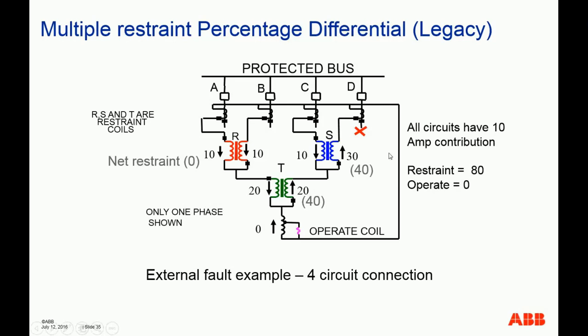I can't discuss too much, but the idea is, when the current passes through the restraint winding in the same direction, the net restraint is 0. So basically they are subtractive. If the currents pass through the windings in different directions, as in this case, then their resulting restraint effect is additive. So in this case, for the external faults, you can see you have the high restraint current.